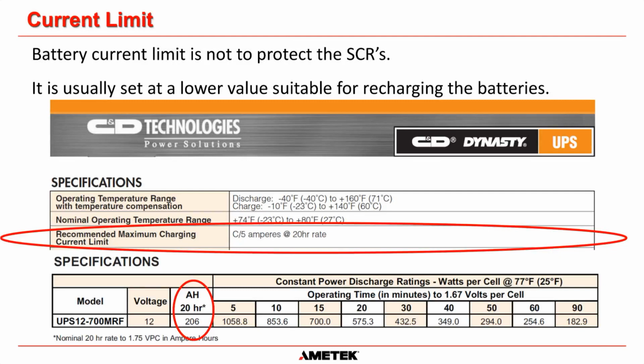What's the minimum recommended conductance to consider when testing batteries with a battery analyzer? I cannot answer that, Denise, because it is all battery specific. The bigger the battery, the more substantial the plates are, whether the plates are made of lead or pure lead, all affects how that battery's conductance or resistance is. So there is no true answer to the minimum recommended conductance, unfortunately.